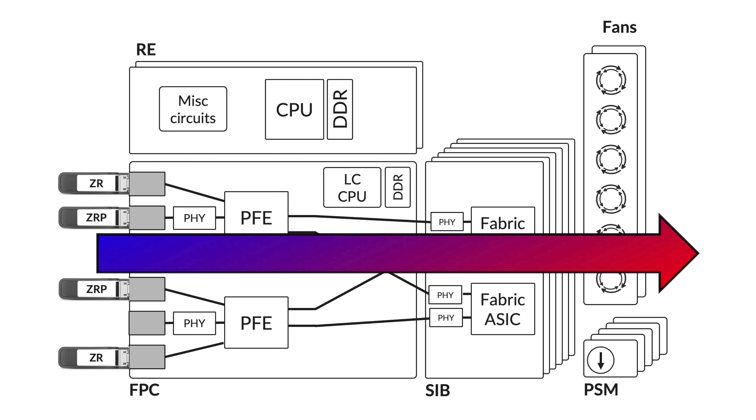It's important to treat high power optics as a specific case: they will preheat significantly the airflow entering the router, which has an important impact on the leakage power of all internal components. Consequently, when measuring the power used by a system, you cannot test in your lab with a router wired only with DAC or AOC interfaces and then add up the power used by high power optics — like 22 or 25 watts per port. That will not be an accurate estimation, because with low power optics the internal chassis temperature is much lower, and consequently leakage power is lower. You need to execute a specific test with high power optics to be realistic.